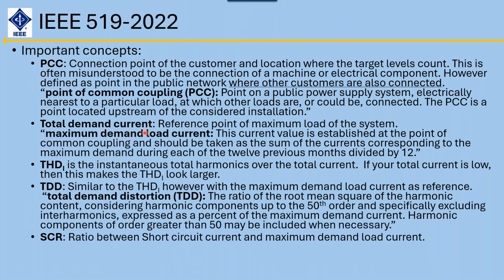We're going to talk about total demand current, which is used for what we call TDD, which is how much current is in the system, versus THDI. I've got a better slide on this, but this is what the standard now uses as a reference point. THDI is the instantaneous harmonics over the current, and there's a picture of that. TDD is what the new standard refers to, and they want you to compare everything to TDD. THDI can come up as a big number, whereas TDD should always be more realistic. And then SCR is the short circuit ratio, which is our short circuit current over the maximum load. We'll talk more about that, and I've got an example.